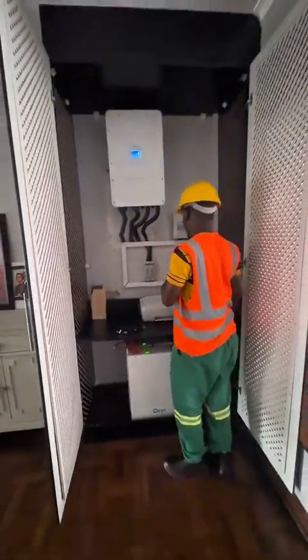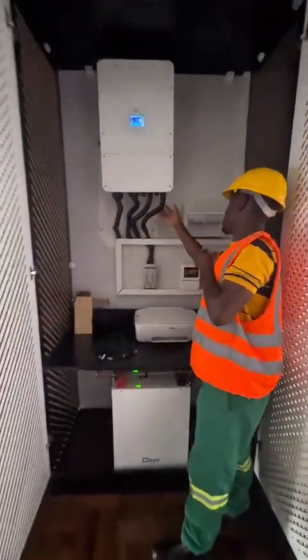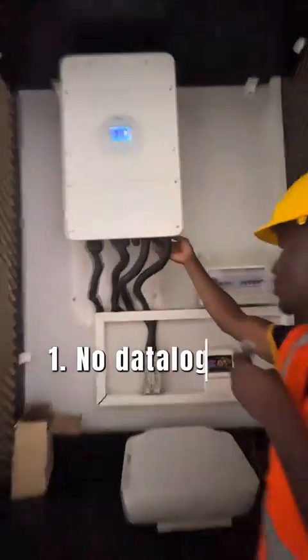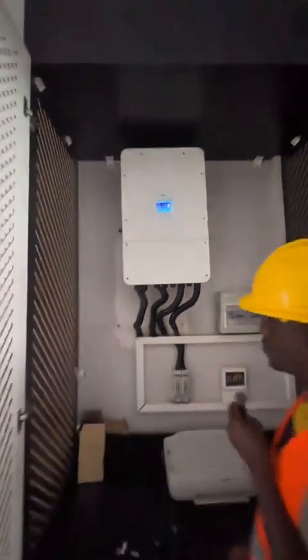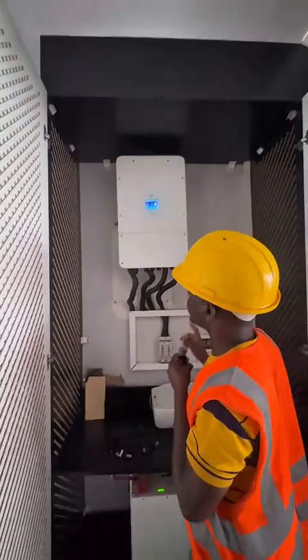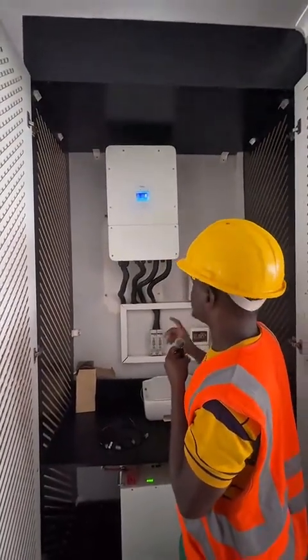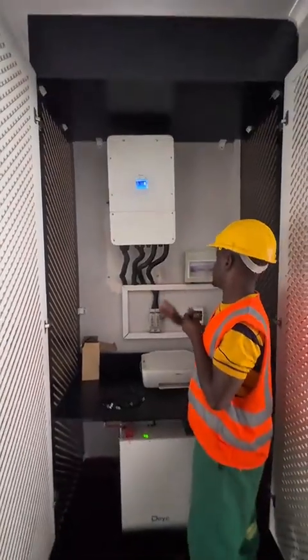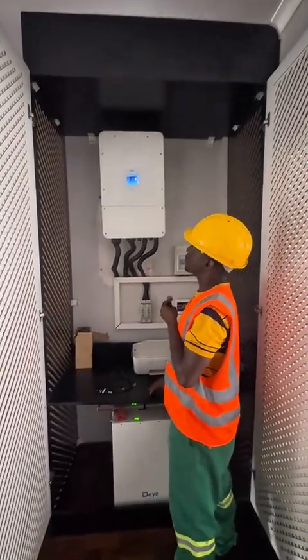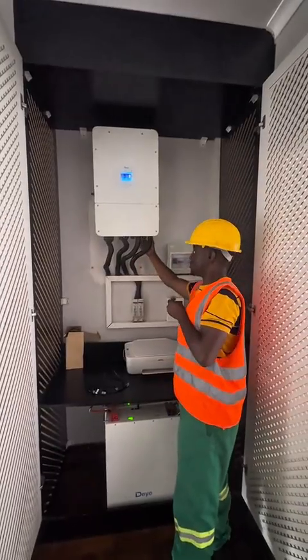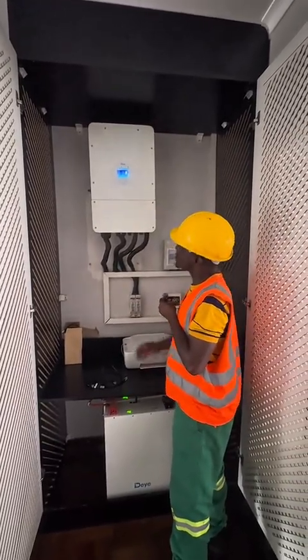Okay, good. So the first thing that we saw before even touching anything was that there is no data logger here. So we didn't do this installation, but the data logger clearly wasn't installed on this system, and we highly advise always installing a data logger, especially if the client has Wi-Fi on premises, and this client does have Wi-Fi on premises, so there was no reason for not installing this data logger.